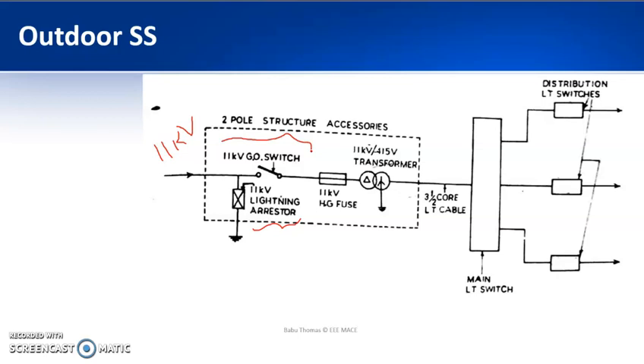And then we will have an 11 kV horn gap fuse. It is called a horn gap because it looks like a horn. That is similar to a normal fuse which you have at a house, but it is for an 11 kV supply system. From there it is taken to a transformer, which is an 11 kV by 415 volt transformer, and from the transformer, through a 3.5 core LT cable, it goes to an LT switchboard, the main LT switch, which will have a switch fuse unit in order to protect against any kind of fault occurring downstream of your transformer.